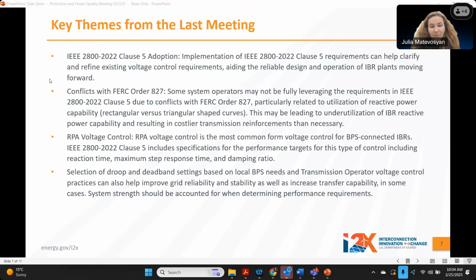So just a few key themes from the last meeting. As I said, we talked about Clause 5 adoption. This requirement can help clarify and refine existing voltage control requirements and aid reliable design and operation of inverter-based resources going forward. Sometimes conflicts between FERC Order 827 and Clause 5 may result in not fully leveraging capabilities of inverter-based resources, particularly related to rectangular versus triangular shaped curves. This may be leading to underutilization of IBR reactive power capability and may result in costlier transmission reinforcements than are necessary.